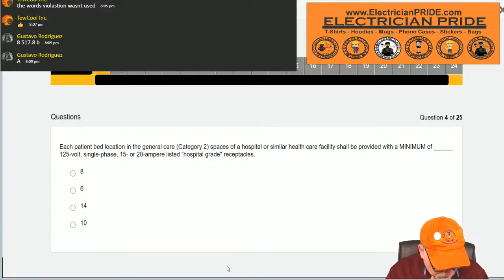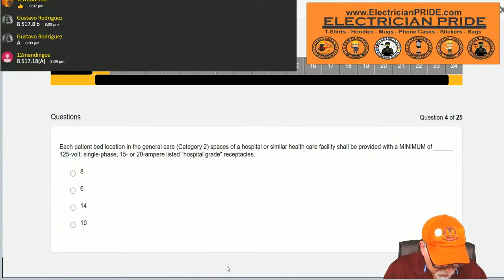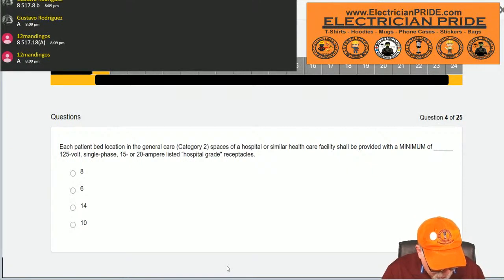Keep looking—receptacles. Okay, under receptacles, remember my little scratch paper? All right, Gustavo, give me a code reference. So notice that under receptacles, it's 517, so we know we're in 517. But notice it says 13, 16, 19, 31, and 42—those are the code sections. I am literally going to write those down. Remember what I tell you about using the code in your scratch paper? When you go to the back of the index, make sure you spend time back there.